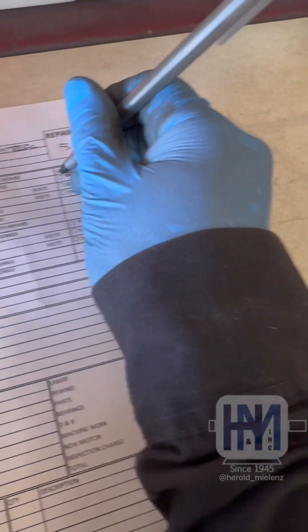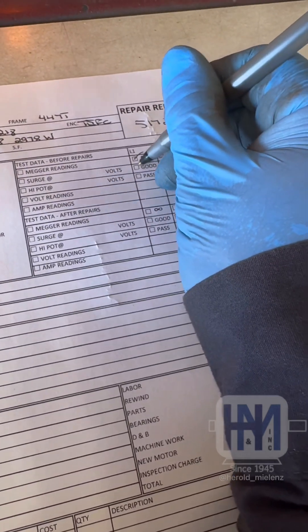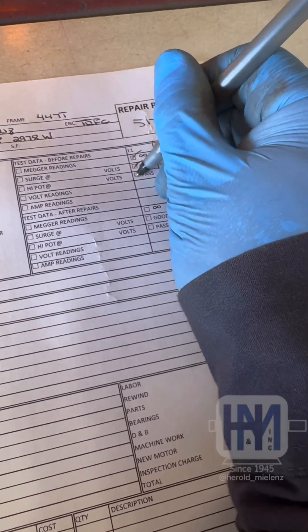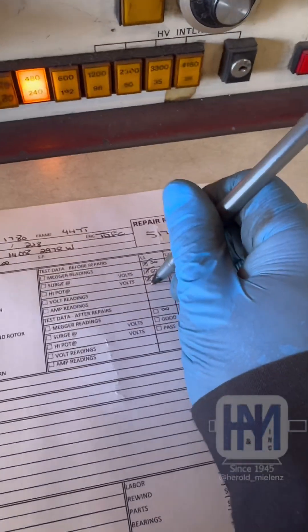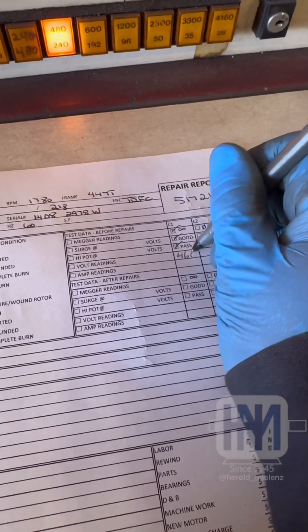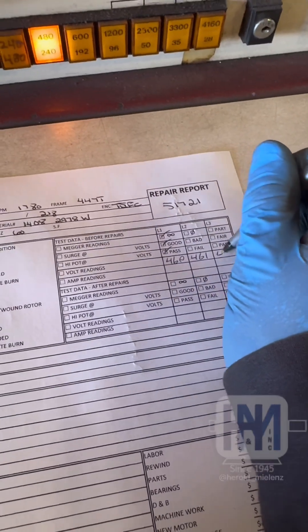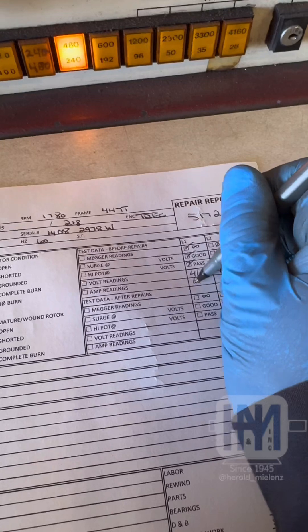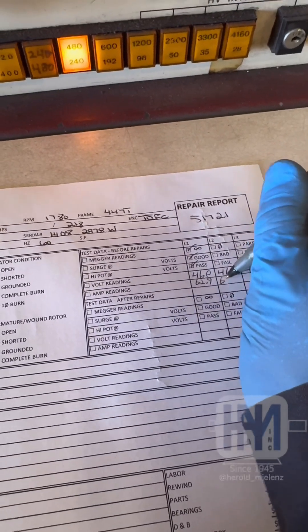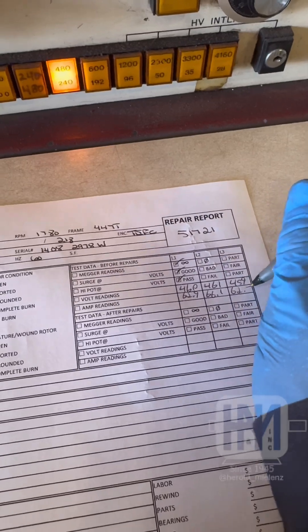I can write it on the job card. Our megger readings: good. Surge is good. Hi-pot was good. Voltage readings: 460, 461, 459 — and 62.9, 66.1, 62.7.